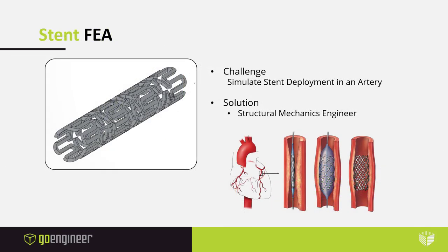For the next example, a very popular case study in the life sciences field: coronary angioplasty — simulating the deployment of a stent in an artery using the structural mechanics engineer role, which is the Abaqus solver on the 3DEXPERIENCE platform. This basically involves three steps: deploying the catheter in the area of the artery requiring the stent, expanding the balloon to expand the stent, and then the stent crimping onto the artery wall. The goal is to see the stress distribution of the stent and evaluate the efficacy of this entire process.